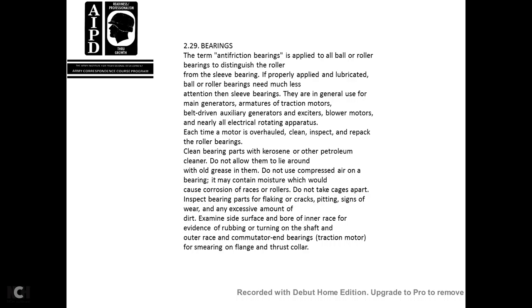Do not use compressed air on a bearing, as the moisture it contains would cause corrosion of the races or rollers. Do not take the cages apart. Inspect the bearing parts for flaking, cracks, pitting, and signs of wear, and any excessive amount of dirt. Examine the side surface and bore of the inner race for evidence of rubbing or turning on the shaft, outer race of the commutator end of the bearings, traction motor, for smearing on flange or thrust collar.